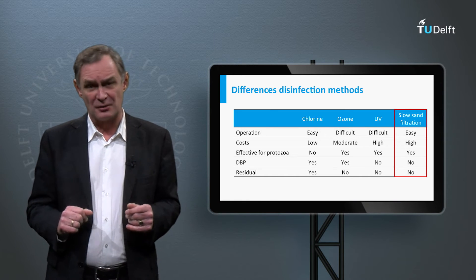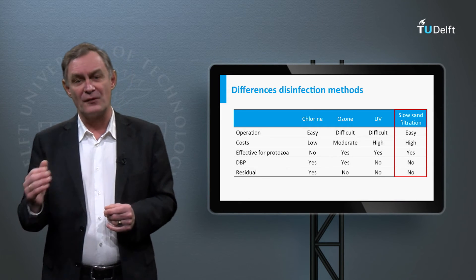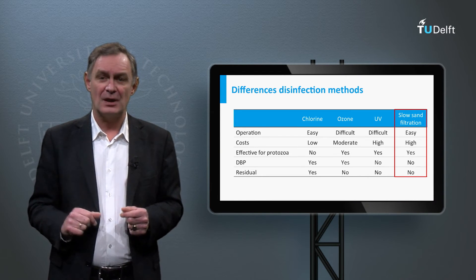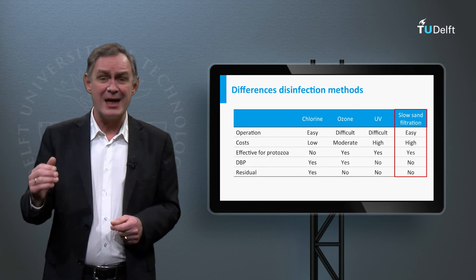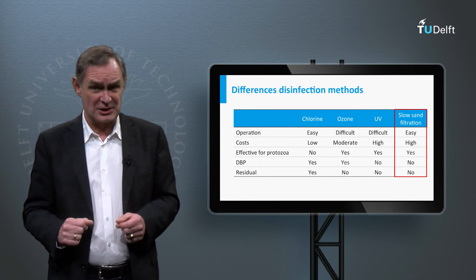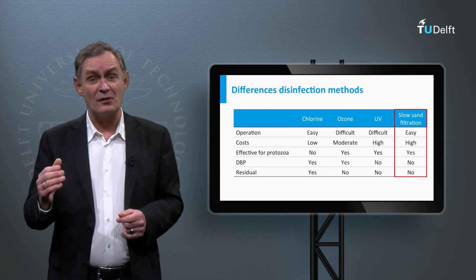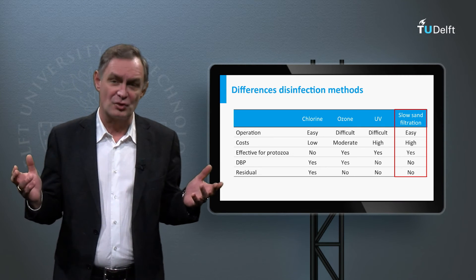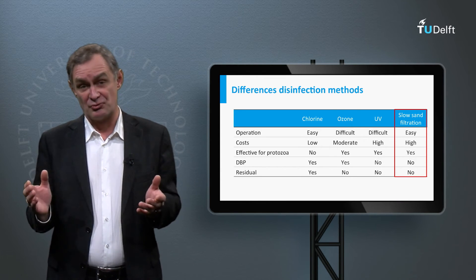Slow sand filtration is a simple process to operate, but relatively expensive to build because of the large footprint. It removes the microorganisms from the water by filtration, sieving, adsorption, and decay. It is also effective in removing microorganisms and can reach 99 to 99.9% removal. An advantage is that disinfection by-products aren't formed, but it also lacks the formation of a residual to prevent regrowth. This is, however, compensated by the high degree of nutrient removal during the process, also diminishing the regrowth potential.